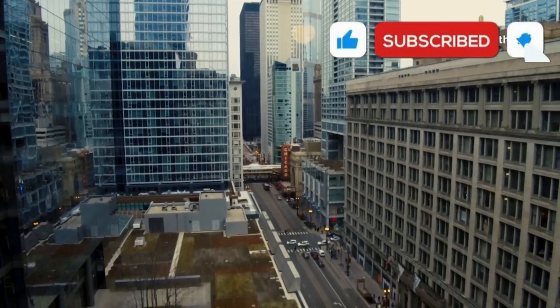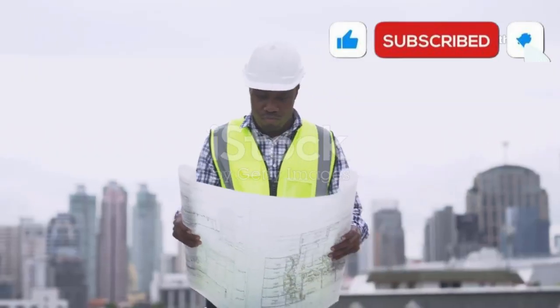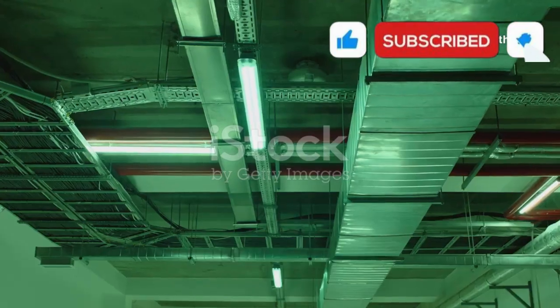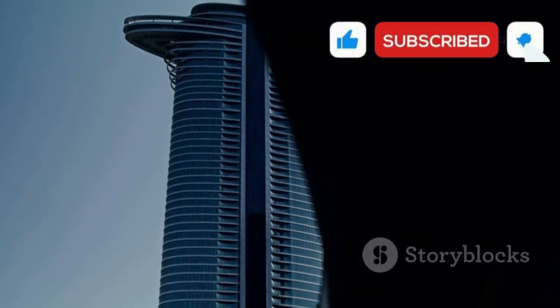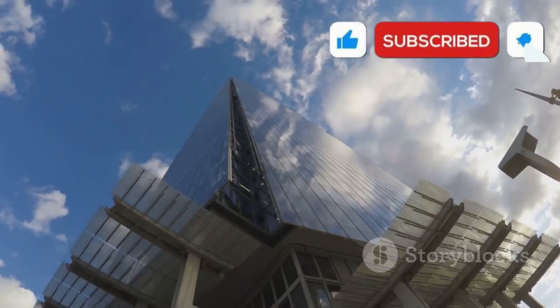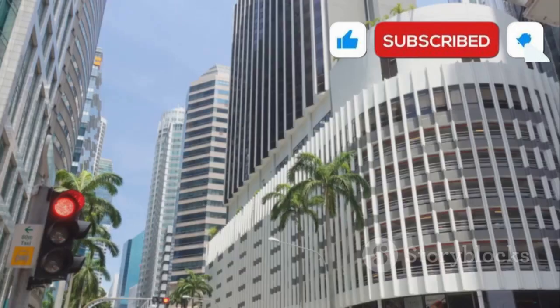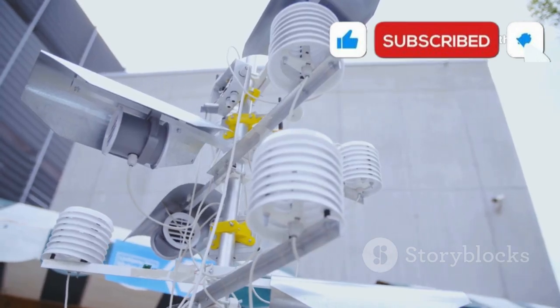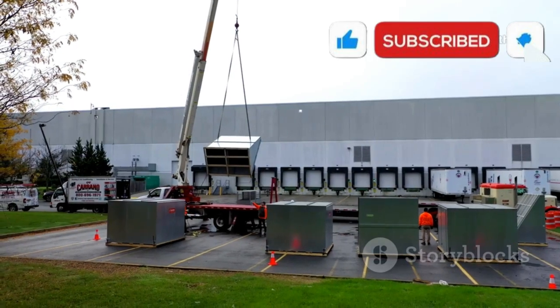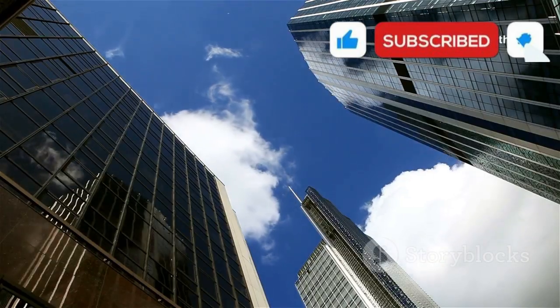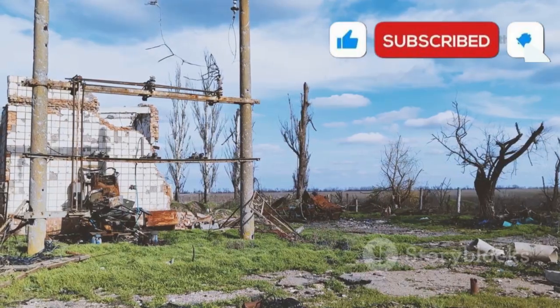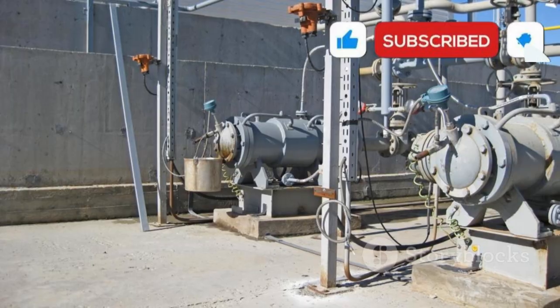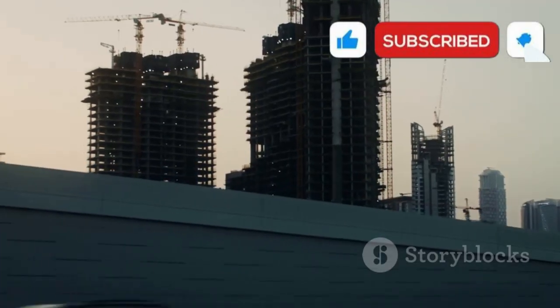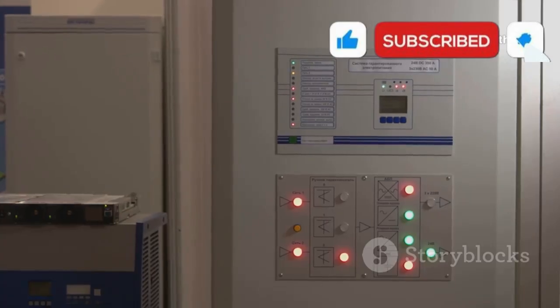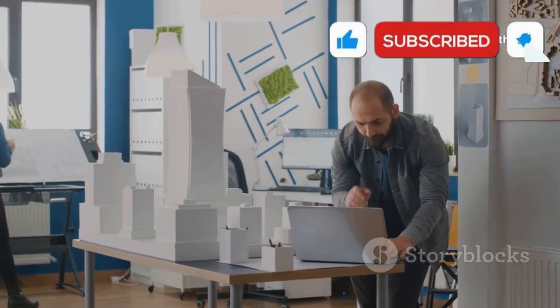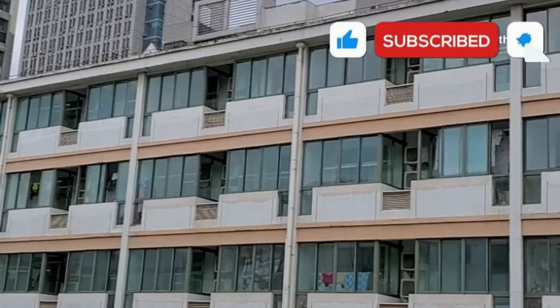Every building faces its own unique challenges. Designing a skyscraper's cooling system is a complex puzzle. Local climate is key. A building in Dubai faces different challenges than one in London or Singapore. Sun intensity, outdoor temperature, and humidity all dictate the size and type of cooling equipment. The building's height adds more complexity. Pumping water hundreds of meters up requires powerful pumps, and the stack effect can cause temperature imbalances. Engineers use zoned systems and sophisticated modeling to keep temperatures consistent from bottom to top.